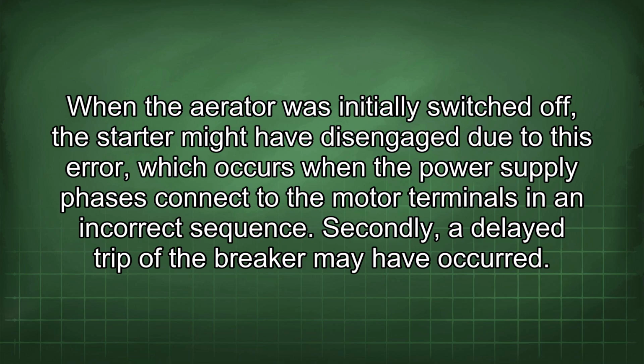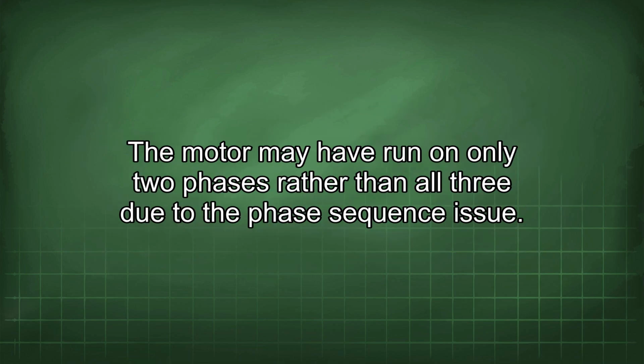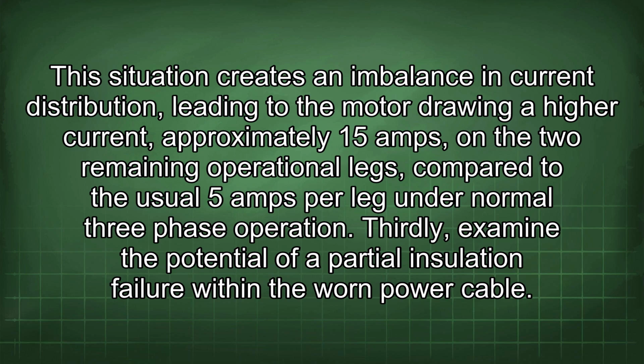Secondly, a delayed trip of the breaker may have occurred. The motor may have run on only 2 phases rather than all 3 due to the phase sequence issue. This situation creates an imbalance in current distribution, leading to the motor drawing a high current, approximately 15 amps, on the 2 remaining operational legs, compared to the usual 5 amps per leg under normal 3-phase operation.